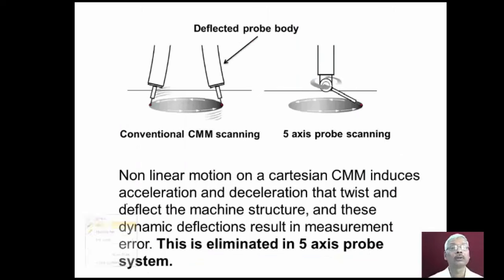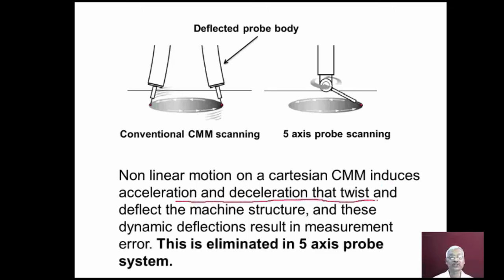Non-linear motion on a Cartesian CMM induces acceleration and deceleration that twist and deflect the machine structure, and these dynamic deflections result in measurement error. This is shown by a deflected probe body when using a conventional probe, compared to a 5-axis scanning type probe. This problem is eliminated by using the 5-axis probe system.